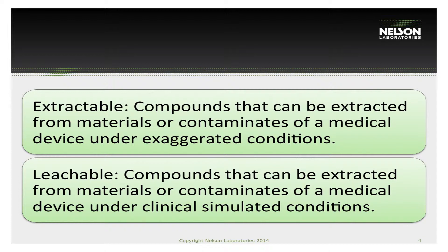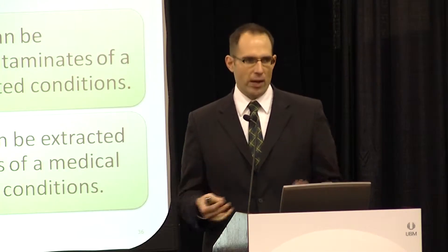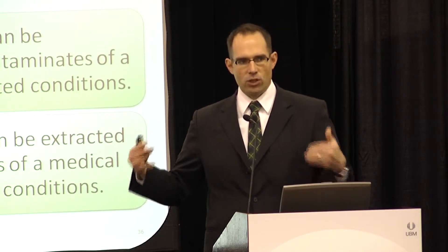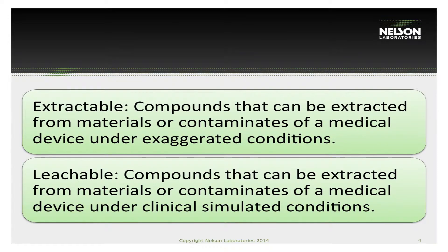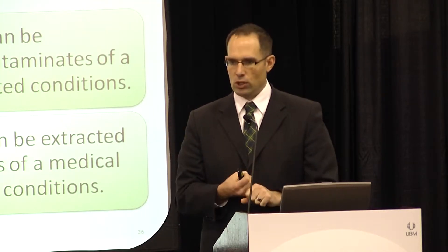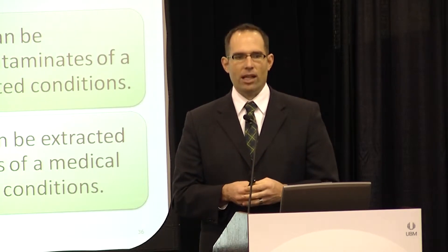Extractables are chemicals that can come off your device under exaggerated conditions. We can either increase the temperature and time of extraction, or use a very harsh solvent to get as many chemicals off your device as possible. Leachables are chemicals that come off your device under clinically simulated conditions — we look at your device and mimic the time, temperature, and solvents involved in the clinical use.